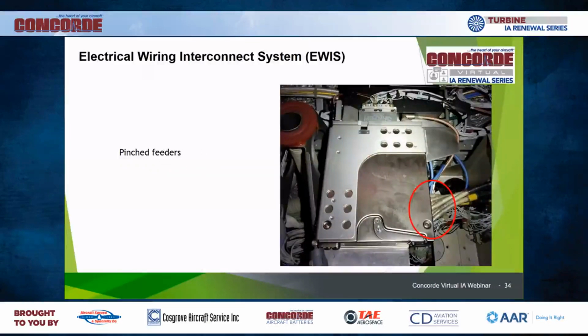Pinched feeders—this one was under the floor again, with no protection between the edge of this metal cover and the feeders themselves. This happens a lot. There are heavy feeders in the area with even smaller wires behind them, and those smaller wires look very rat's-nesty. Protection between the large, heavy current cables and those smaller cables is imperative as well.